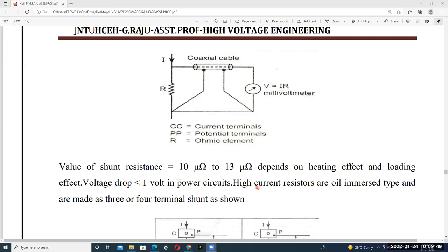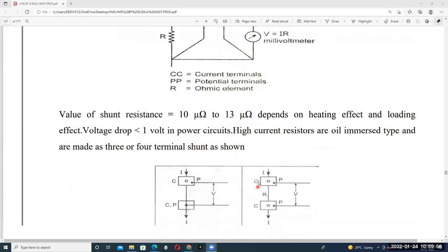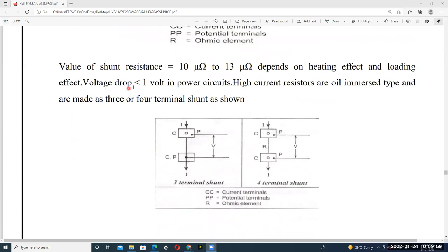High current resistors are oil-immersed type and are made with three or four terminals, as shown here. To avoid excess voltage drop, the voltage drop must be maintained below one volt. This is a four-terminal shunt and this is a three-terminal shunt. CC represents the current terminals and PP represents the potential terminals, and R is called the ohmic element.